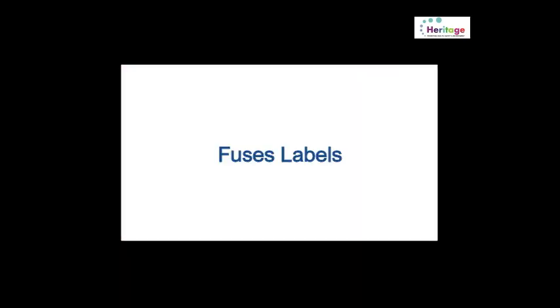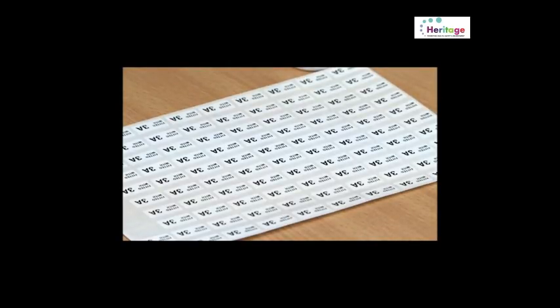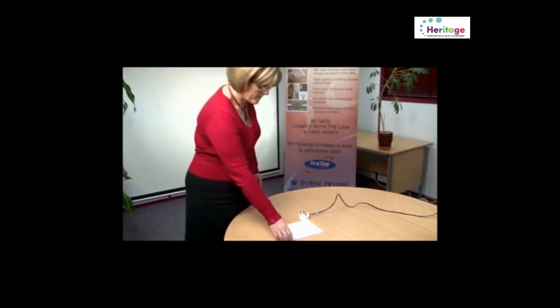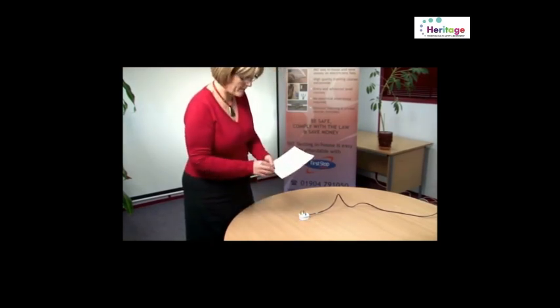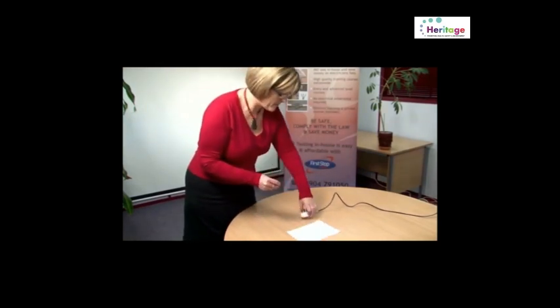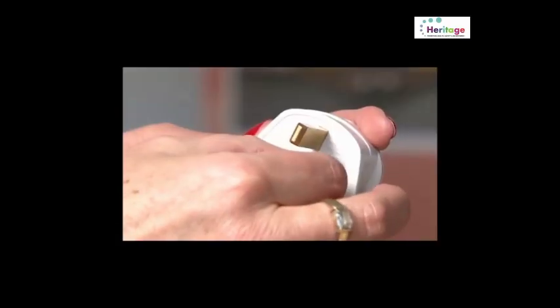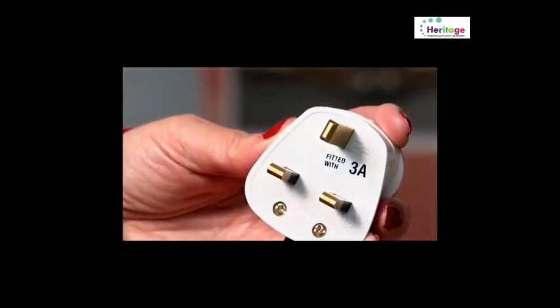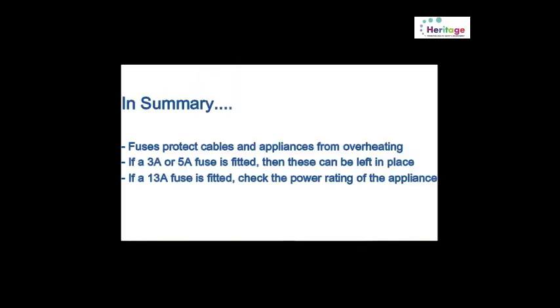Fuse labels. Once a plug has been checked for the correct value of fuse, it's good practice to seal the plug. If on future inspection this seal is intact, then this is a good indication that no one has tampered with the wiring or changed the fuse. This will save considerable time during subsequent inspections.